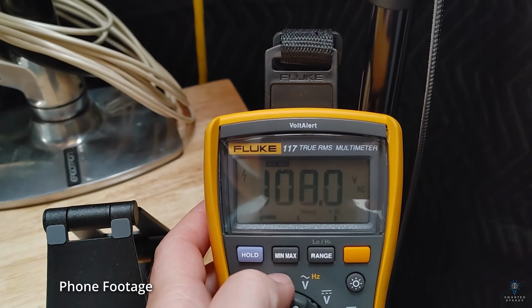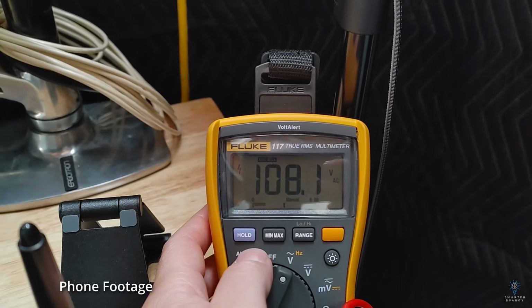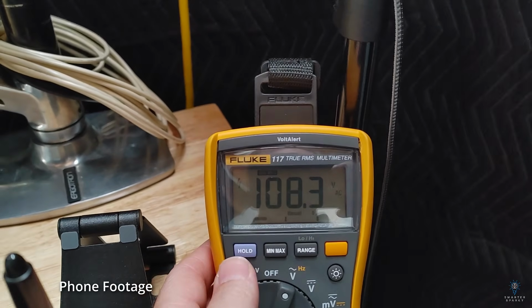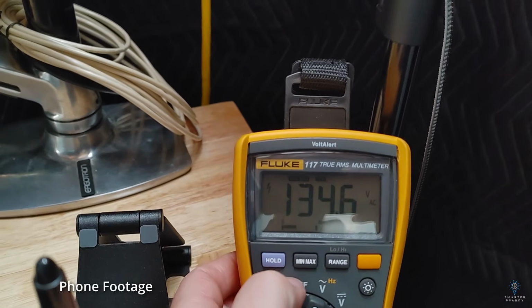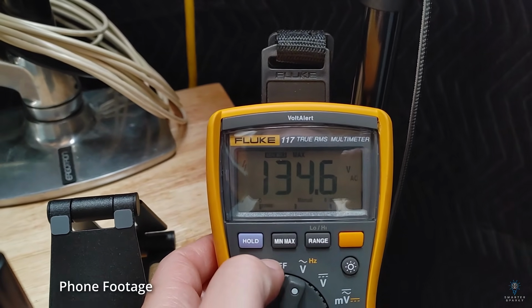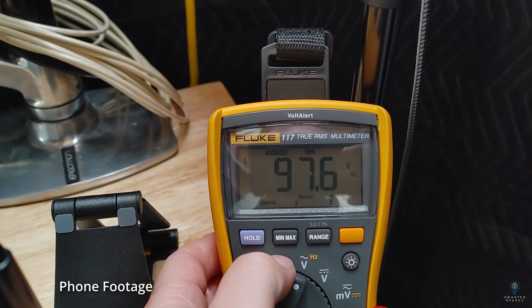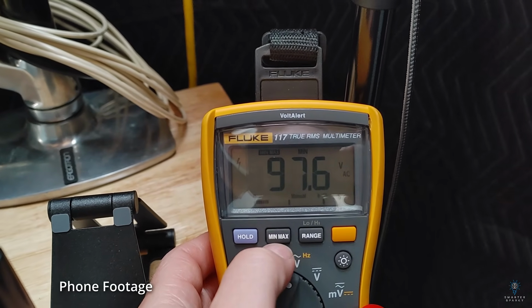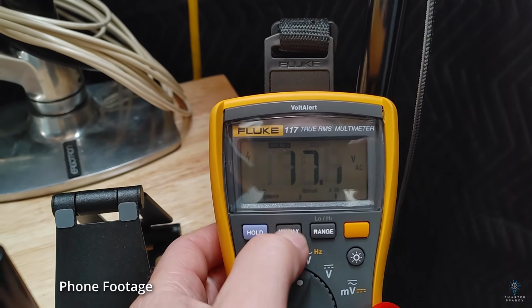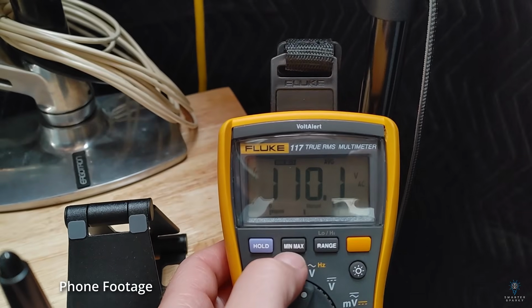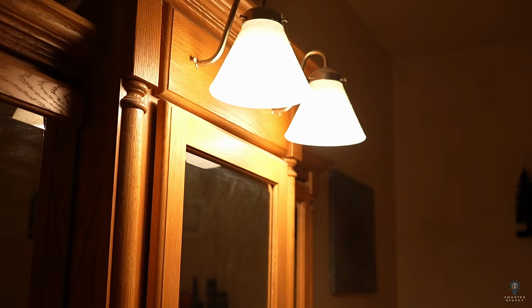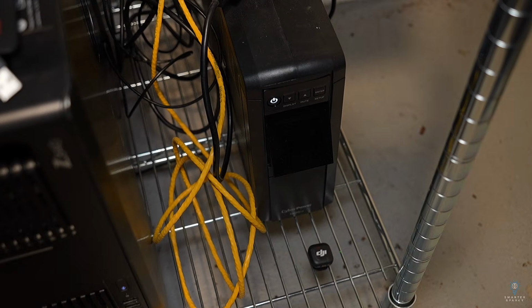Let's see, what is it now? 108 volts right now. I mean, it should be 120 volts right now. Again, maximum 134.6. 97.6 is the minimum. Very large voltage swing there. What is that? Almost 40 volts. Average has been 110. Additionally, the lights in my bathroom were flickering and getting brighter or dimmer, and the UPS for my server cycled hundreds of times that day.